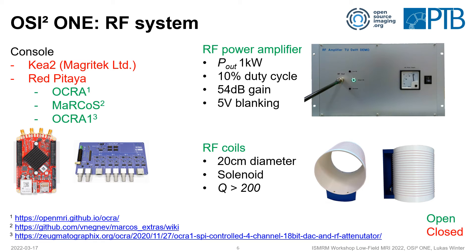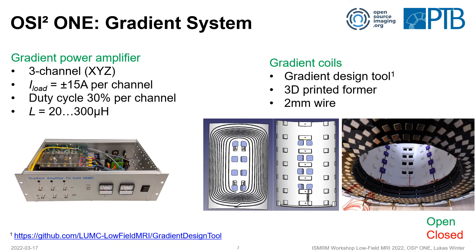There are several RF coils available — basically solenoid coils. You have 3D printed formers that you can use to wind your RF coils. For the gradient system, we have a three-channel gradient power amplifier, also an open source hardware design, with plus/minus 15 amps per channel and 30% duty cycle, which can be used with different gradient coils. The gradient coils are based on an open source software gradient design tool, which is transformed into a CAD model — you can 3D print it, insert wire and glue it, and then insert the X, Y, and Z gradient coils nicely into the magnet.